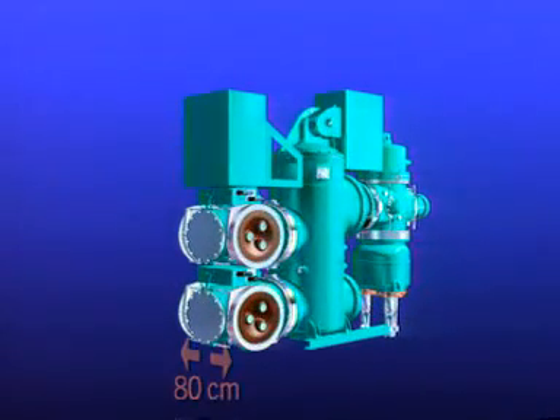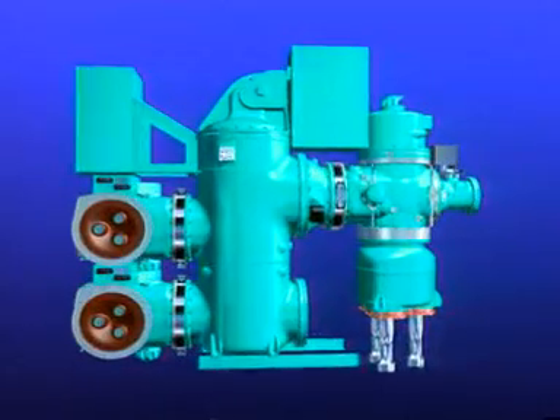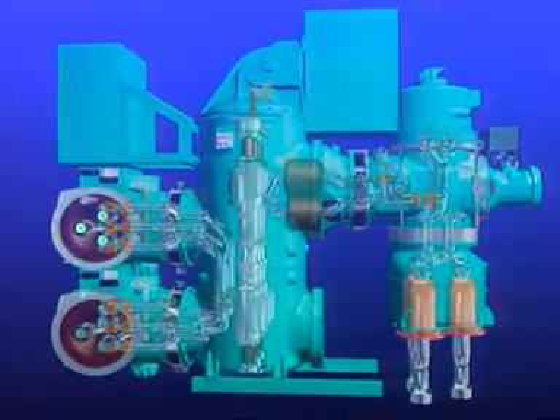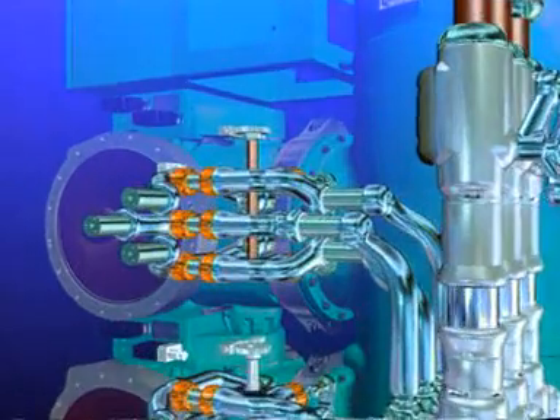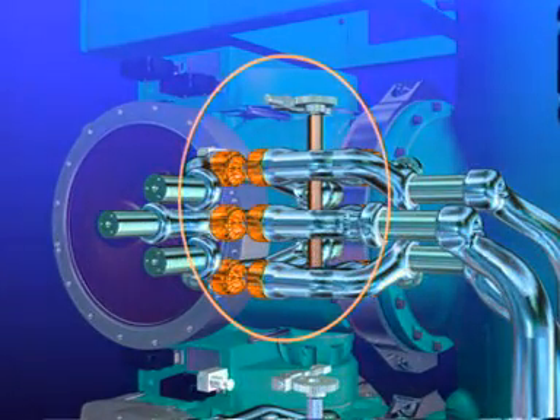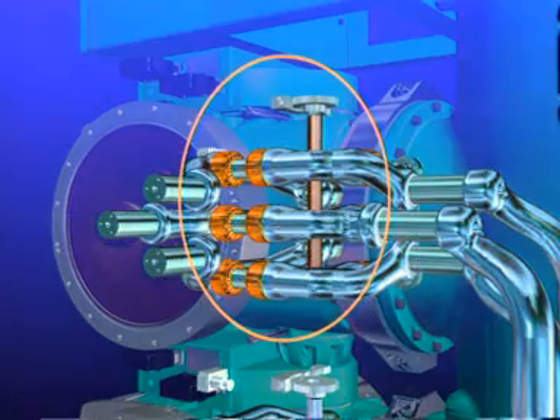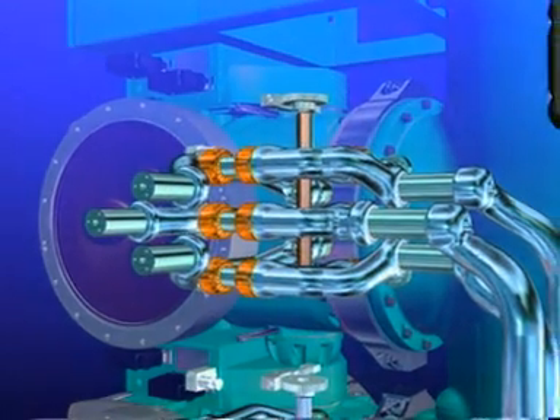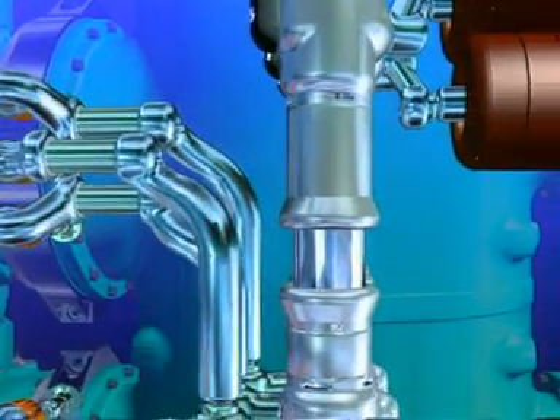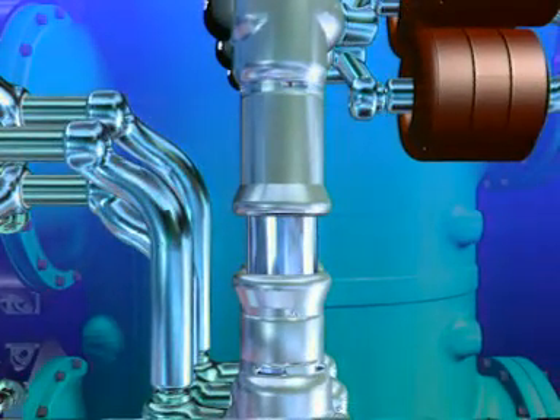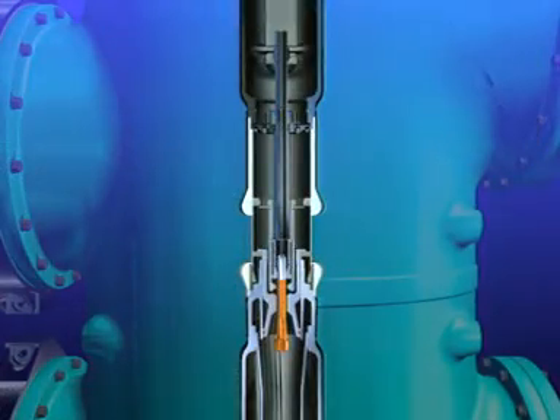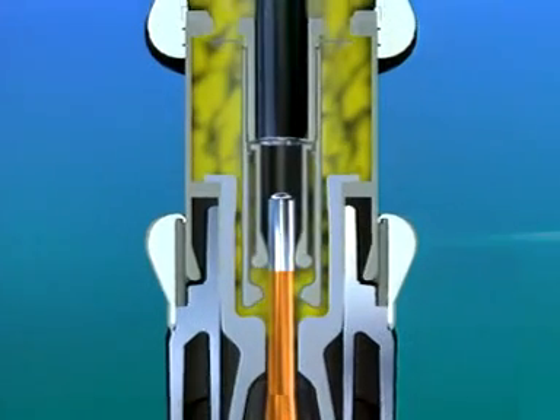The 8DN8 switchgear, for instance, is, with its bay width of 80 centimeters, the smallest system in the world for rated voltages up to 145 kilovolts. This compact design was achieved by triple pole encapsulation of all components within the system. The three-position switching device combines the functions of a busbar disconnector and a maintenance earthing switch. The circuit breaker is the key element in the system. Its interrupter units are installed in a hermetically sealed aluminum enclosure. SF6 gas serves as the insulating and quenching medium.